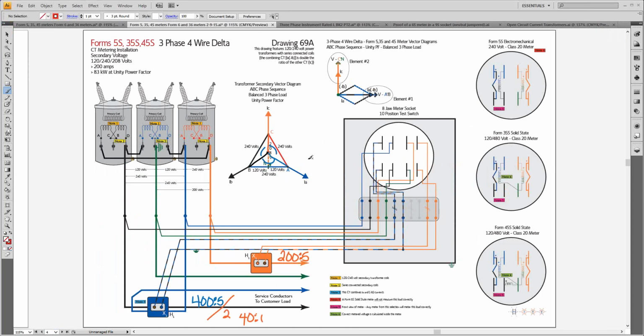And so as I look from the transformer vector to what the meter vector looks like, this is what the meter vector looks like for the two elements of my meter. Element number 1 is in this meter. That's what we'll talk about now. So this is a 2-element meter, element number 1, and then element number 2 here. I'll put a 1 and a 2. So those are 2 meter elements. So element number 1, as far as how the currents are wired in here, IA current goes through the CT in its H1, so it goes in H1, goes out of H2, and then goes off to the load.